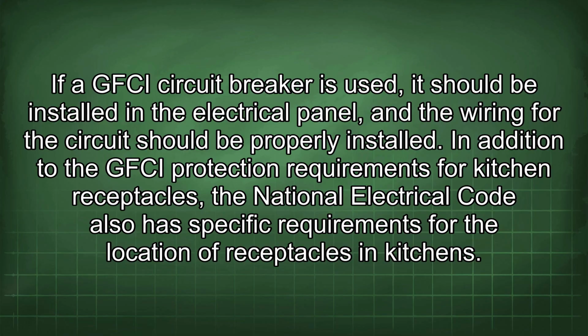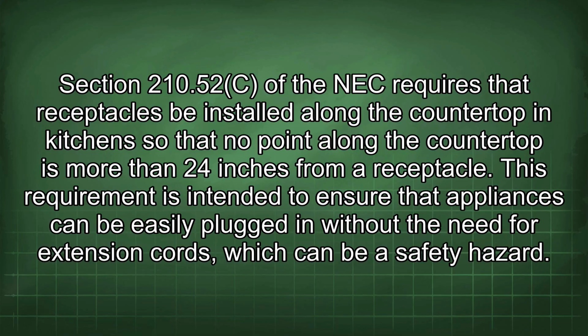In addition to the GFCI protection requirements for kitchen receptacles, the National Electrical Code also has specific requirements for the location of receptacles in kitchens. Section 210.52(C) of the NEC requires that receptacles be installed along the countertop in kitchens so that no point along the countertop is more than 24 inches from a receptacle. This requirement is intended to ensure that appliances can be easily plugged in without the need for extension cords, which can be a safety hazard.